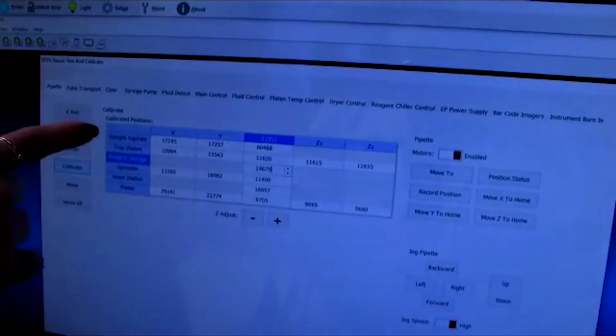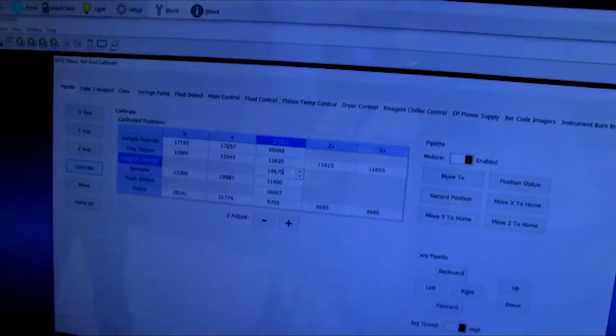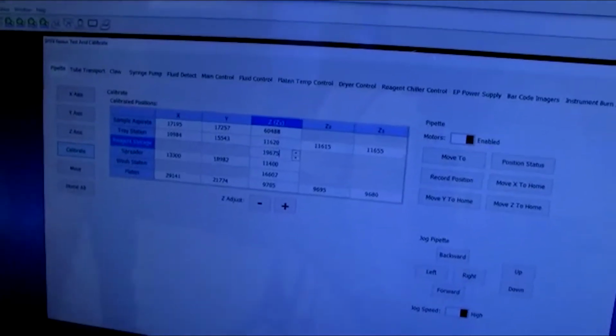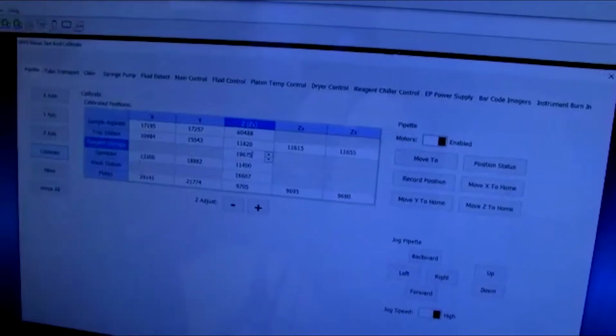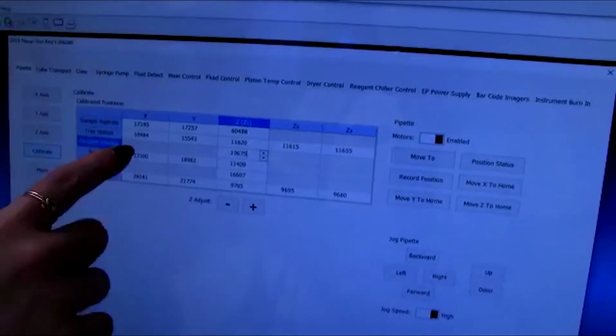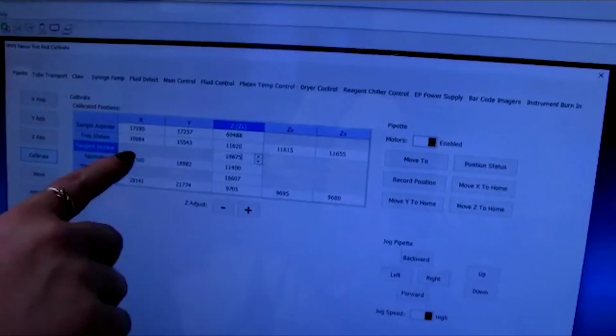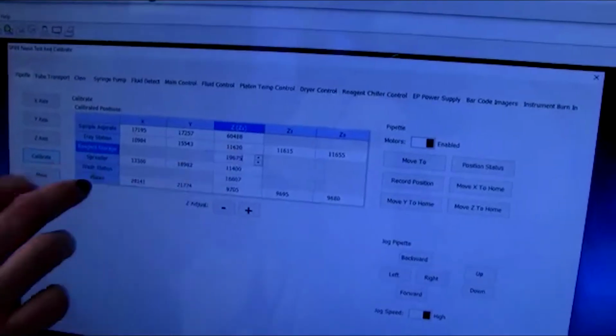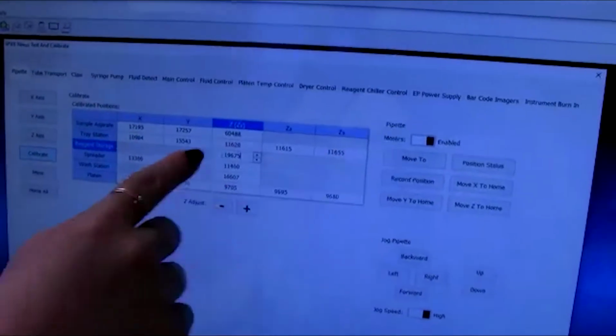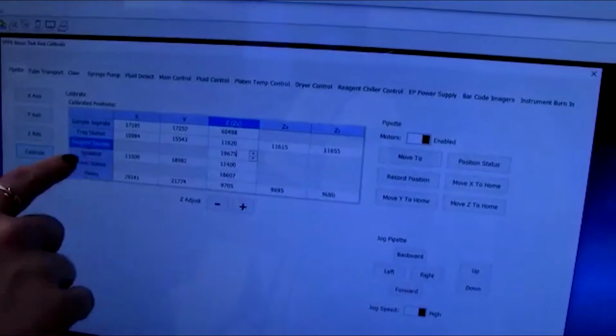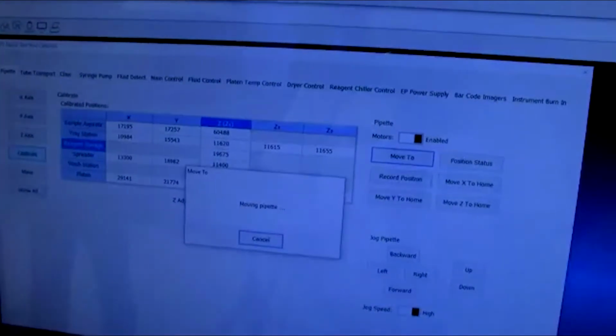I always recommend going in order for the first time you calibrate it, but after that, it's not really necessary. If there's one calibration that needs changing, you don't have to walk through an entire process. You can just go back and manipulate that one number. But for the first time, or when you're checking through it for the first time, I recommend going in order. And this is just a Z calibration. So what I'm going to do now is select this calibration, reagent storage, and press move to.